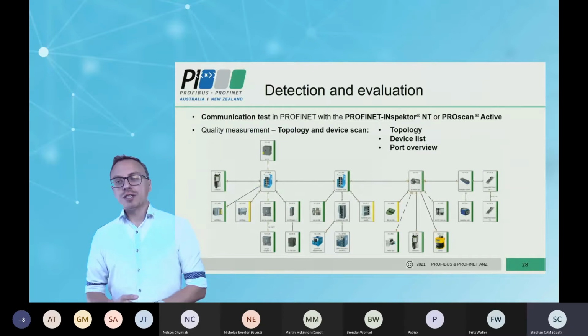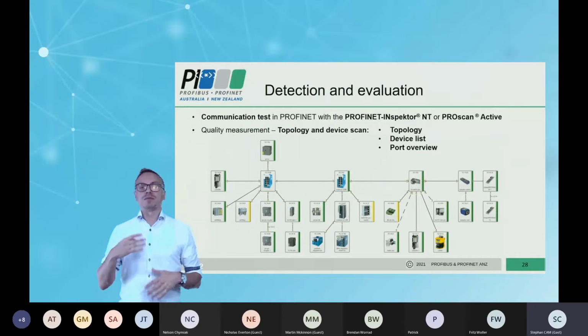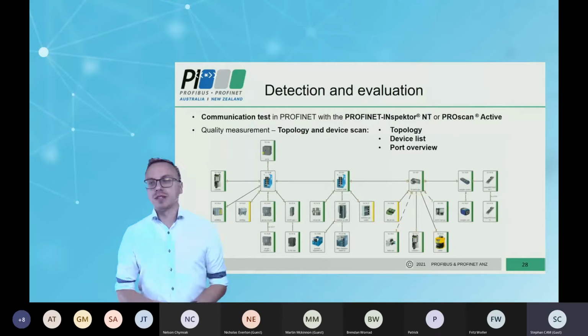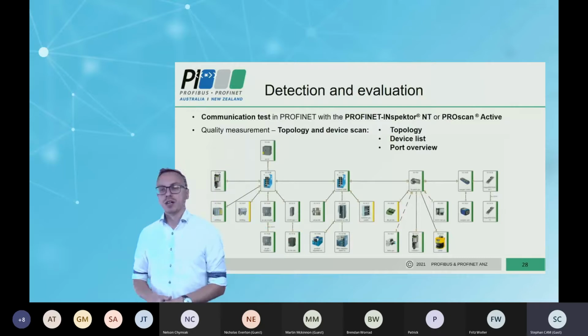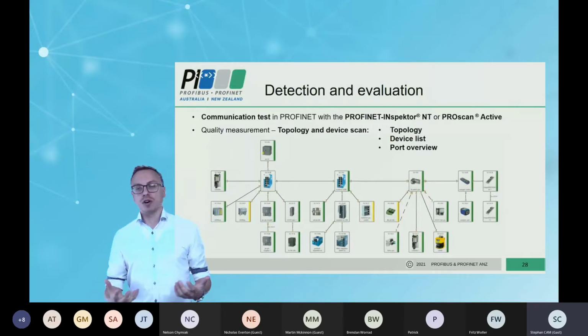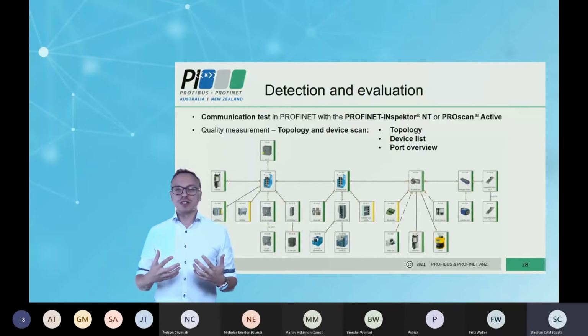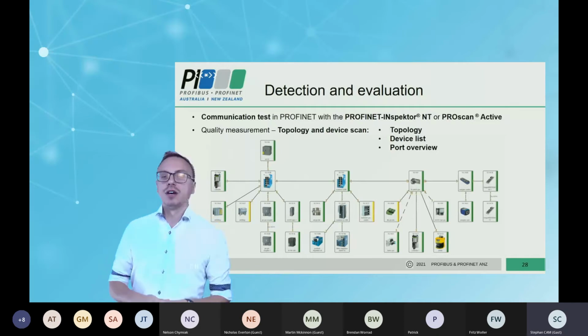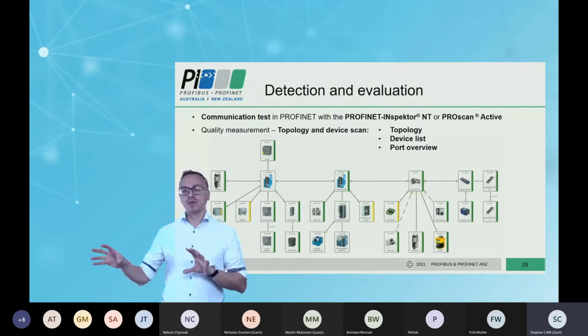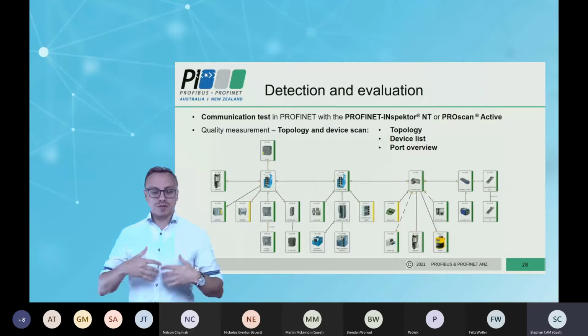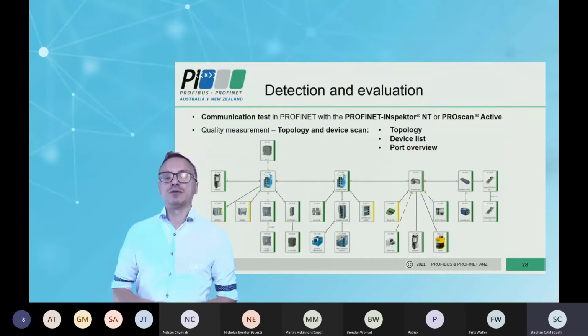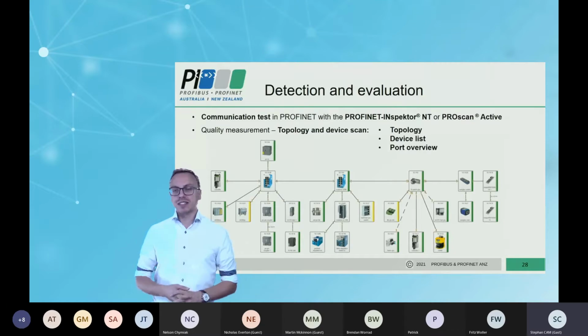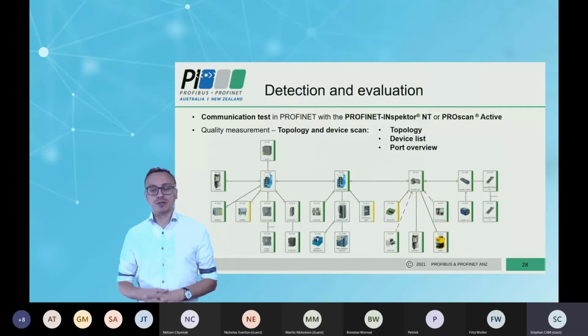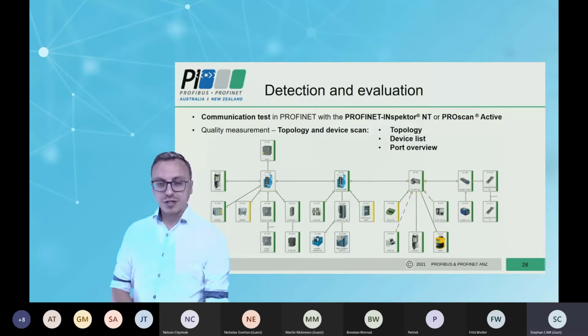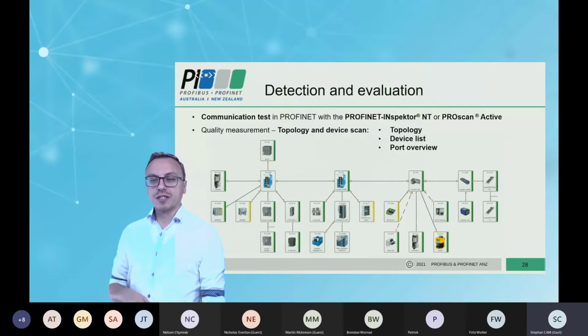Your topology, you can measure it very easily with some scanning tools. For example, you can use ProScan Active or a PROFINET Inspector. Both measurement tools can analyze your topology. This software or these devices will ask over SNMP or LLDP for information, so each device in a conformance class B knows its neighbor. With scanning tools like that, you can analyze your topology very easily, and it's every time up to date. So you get the right topology at the time that you measure. I will show you later a small example of how you can find it out.